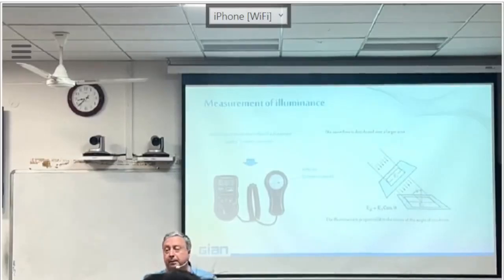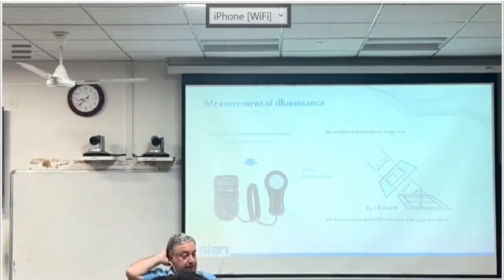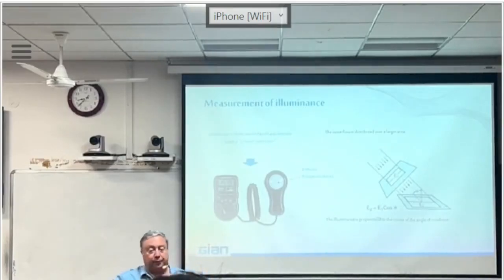And now, I didn't have time, so I asked that to Amazon. There are some small USB lux meters that can communicate with your phone. I bought one for 40 euros from Amazon, and I have checked with another colleague the values that you obtain with that stuff. They are quite correct. But of course you cannot use such kinds of instruments to provide a metrology service. Okay? For you it is fine.